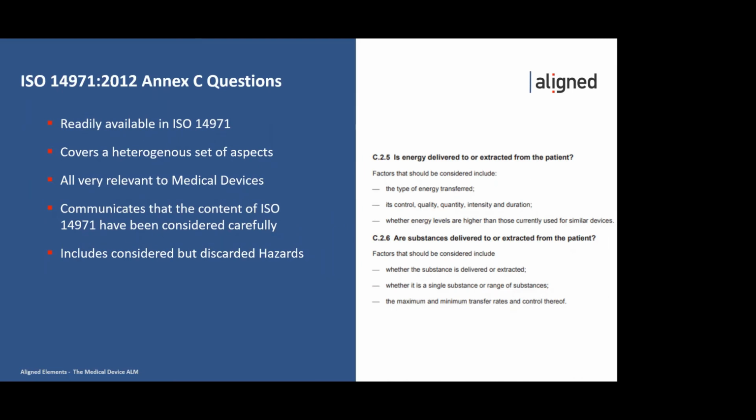And there will be questions that are simply not applicable to your device. But again, it's great to include those and say that I have considered them, but I have excluded or discarded them because they are not applicable. So you can show people that we thought about this, but it's not applicable. We will move on to the ones that are applicable and extract hazardous situations from those.